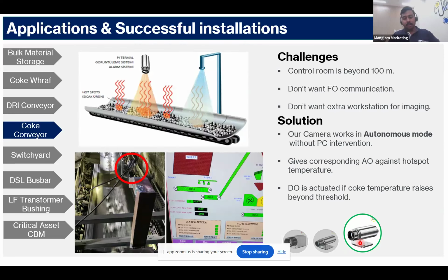Yes, with this AI pyrometer, it is serving quite handy where communication, cable laying, and maintaining a separate PC is quite difficult. You can see the control room is beyond 100 meters, and the customer also doesn't want to lay the FO communications and doesn't want to have an extra workstation for imaging as well. Out here, our infrared pyrometer with AI facilities chips in. It gives a corresponding AO against hotspot temperatures, and DO is also actuated if the coke rises beyond the threshold.